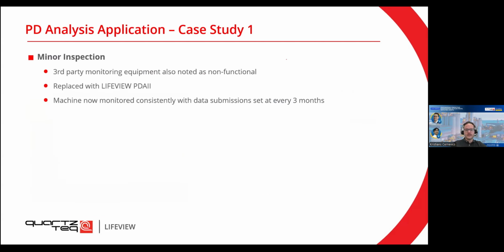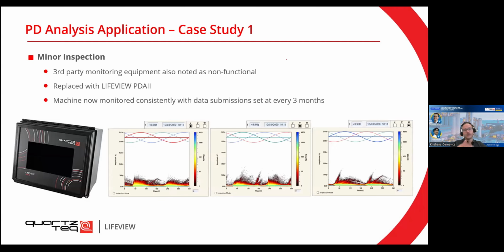What was then also done was that PDA2 was installed, to do this kind of monitoring more regularly. Previous equipment was shown to not be detecting these kind of PD discharges. And what was now happening is that every 3 months, or you can do it every 6 months, the data was sent to be analyzed, so to catch these issues a bit faster. But as we saw now, the partial discharge trends kept quite low.